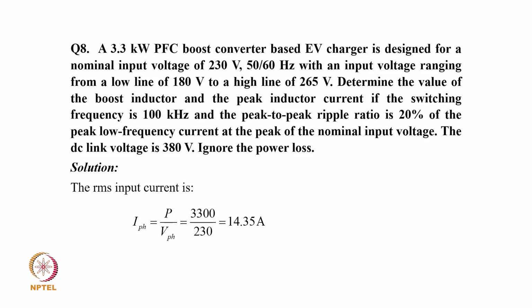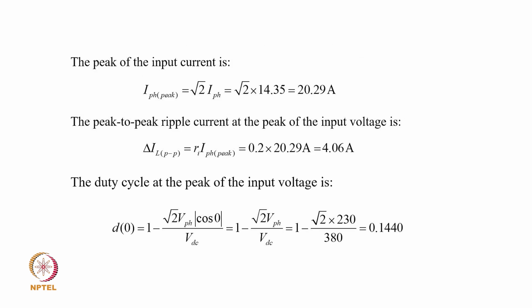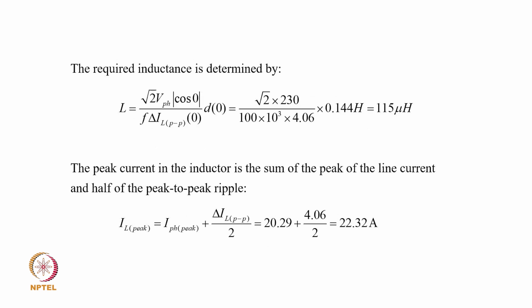The input RMS current IP equal to P upon V, giving 14.35 ampere, and the peak input current I peak is root 2 times IP, giving 20.29. Delta I peak is RI into IP, so 0.2 into 20.29, that is 4.06. The duty cycle at peak input voltage D0 equal to 1 minus root 2 times peak voltage upon VDC, which comes to 0.144. The required inductance L equal to root... using delta F and delta V, putting in values it comes to 115 microhenry. The peak current in the inductor is the sum of the line current, so ILP equal to IP plus delta IL by 2, which comes to 22.32 ampere.